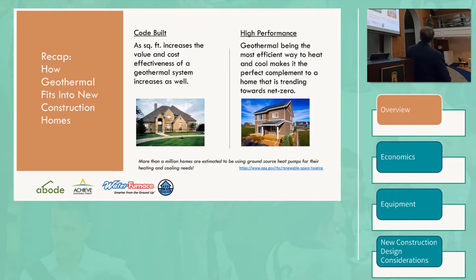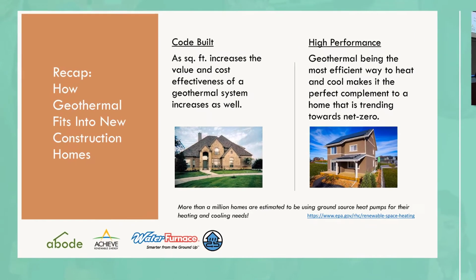So in larger homes, up to the point where we have to put in a second heat pump, the cost per square foot for our install goes down. Then the cycle starts again if there needs to be a second heat pump because the house is larger. But that having been said, even in a small house, if it's very efficient, the ground source install can be relatively inexpensive and have very low operating costs, and it pairs very well, as we'll discuss in a few minutes, with technologies like solar PV.